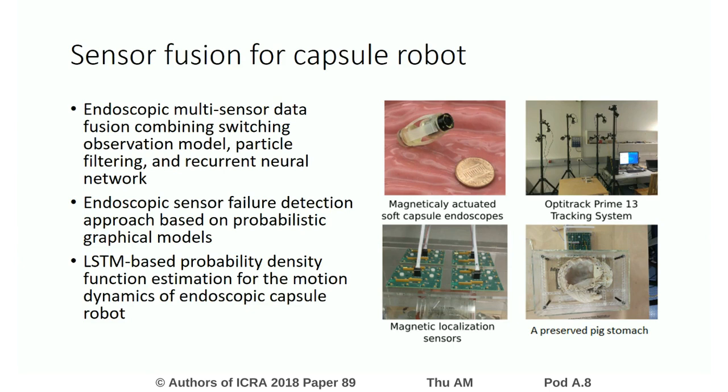We propose a sensor failure detection for capsule robots based on probabilistic graphical models with efficient proposal distributions applied onto the particle filtering, and the approach can be generalized to any number of sensors and any number of robotic platforms. No manual formulation is required to determine a probability density function that describes the motion dynamics, contrary to traditional particle filter and Kalman filter based methods.